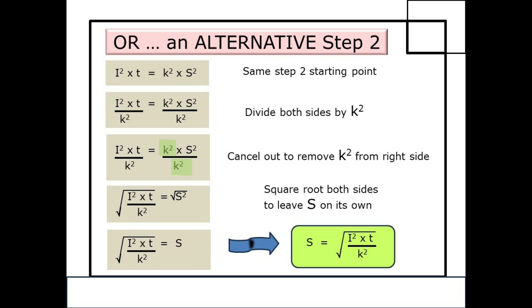There is an alternative solution for step 2, and the question is often asked: are they mathematically different or are they the same? We have the same starting point: I squared times T on the left equals K squared times S squared on the right. This time, divide both sides by K squared and cancel out on the right to remove K squared top and bottom. Now square root both sides — on the right the square root of S squared is just S on its own, since the square and square root cancel. Tidying up: S equals the square root of I squared times T divided by K squared.